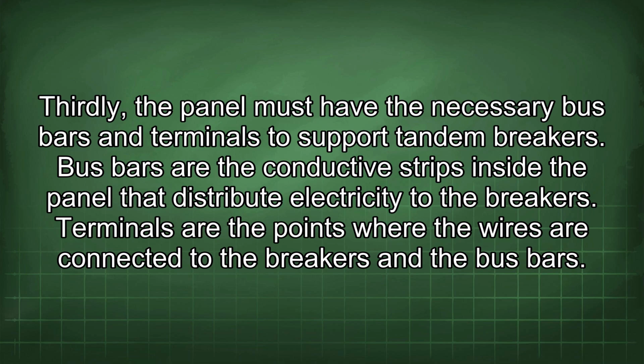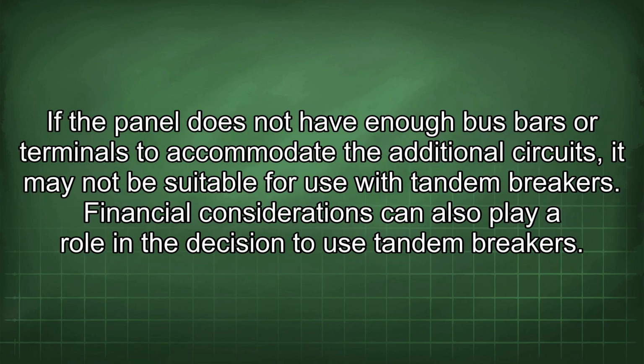Bus bars are the conductive strips inside the panel that distribute electricity to the breakers. Terminals are the points where the wires are connected to the breakers and the bus bars. If the panel does not have enough bus bars or terminals to accommodate the additional circuits, it may not be suitable for use with tandem breakers.